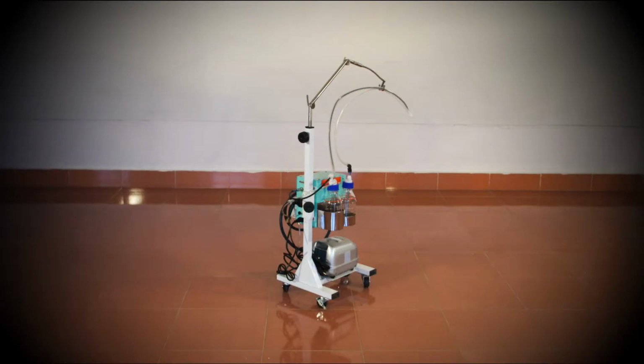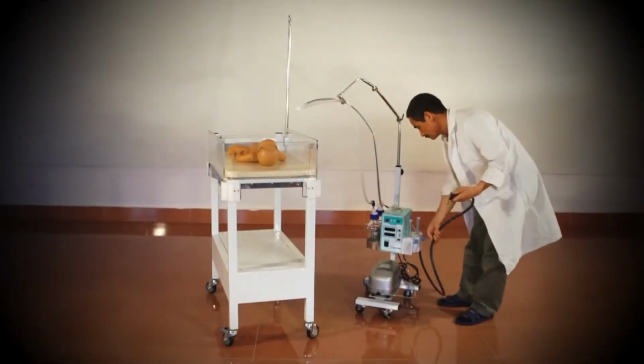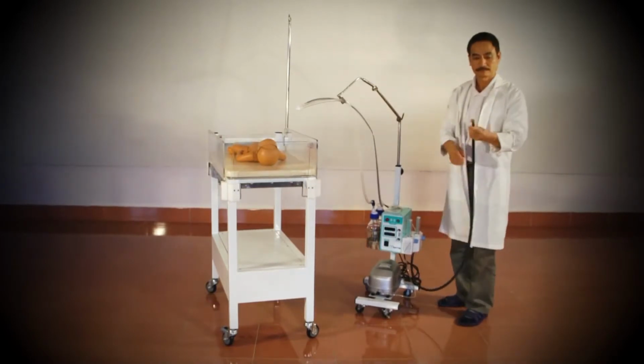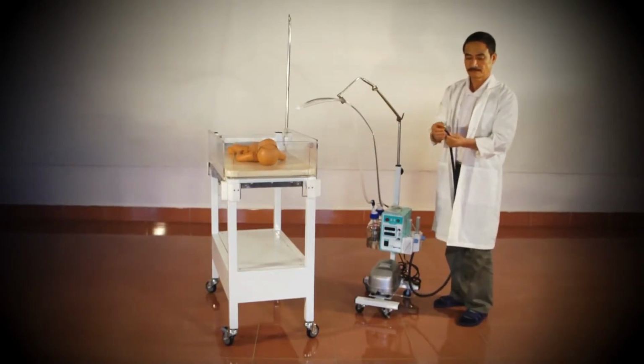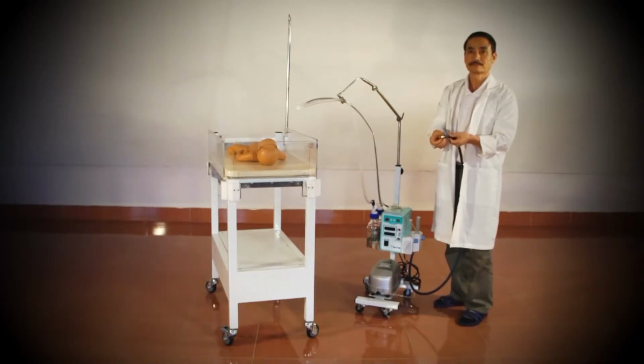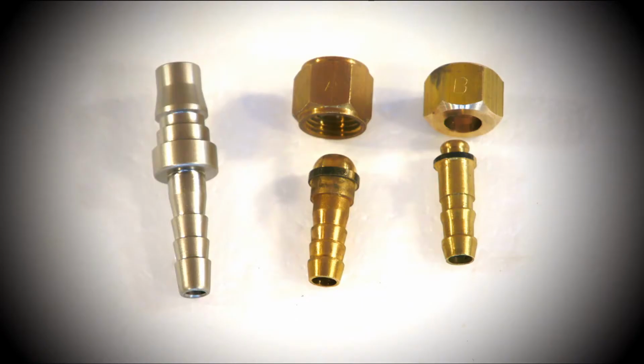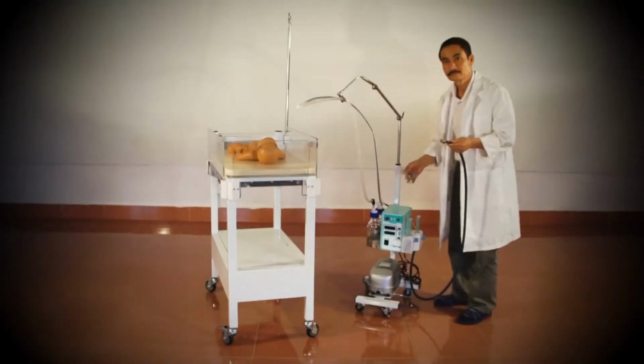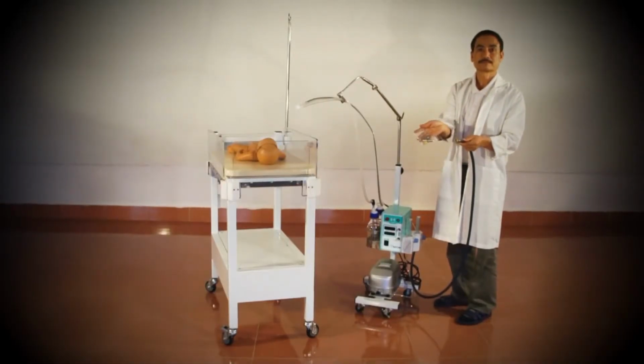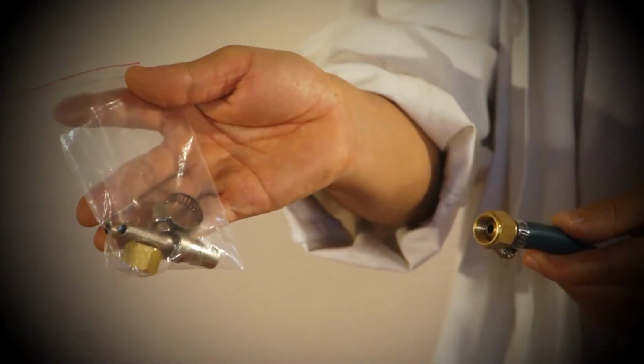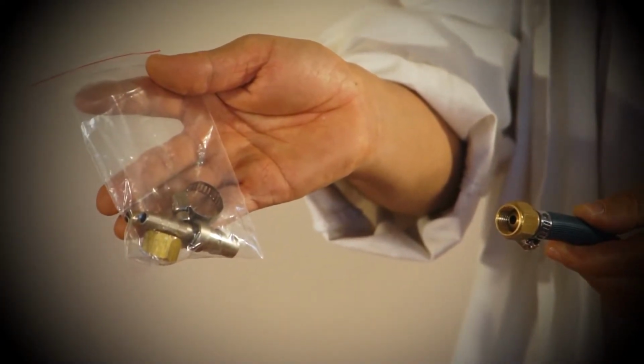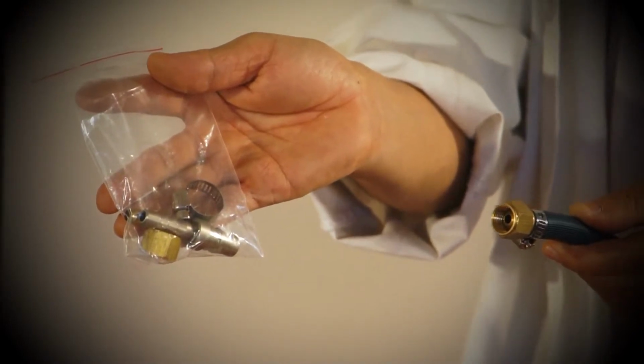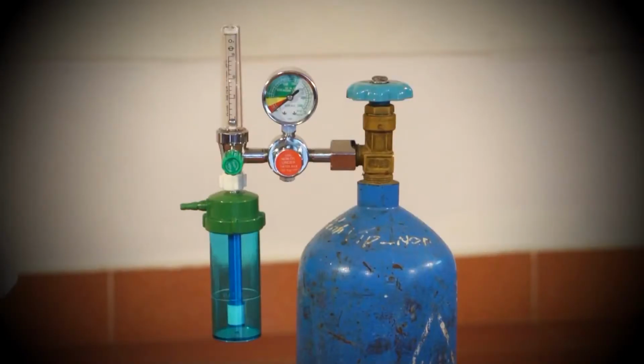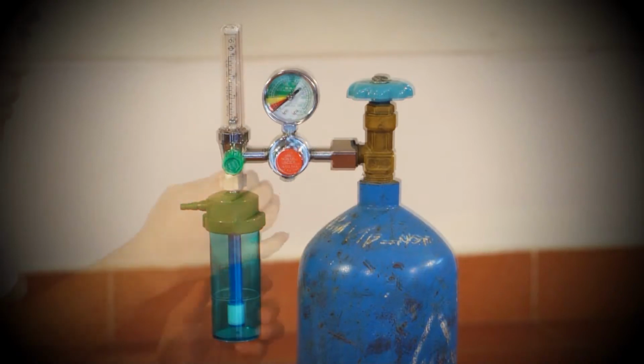The MTTS CPAP can be connected to the 3 most common oxygen sources: hospital wall gas system, oxygen cylinder, or oxygen concentrator. Because different systems require different connectors, 3 common types of connectors are included with each CPAP machine. The most common connector comes attached directly to the oxygen hose. The other 2 can be found in the plastic bag, along with the ring clamp for securing them to the hose. First, we'll cover how to attach the most common connector to an oxygen cylinder.